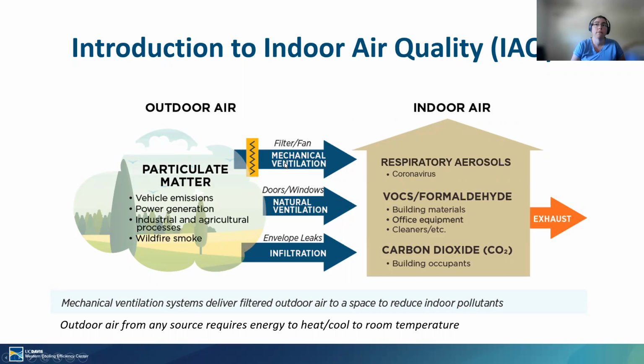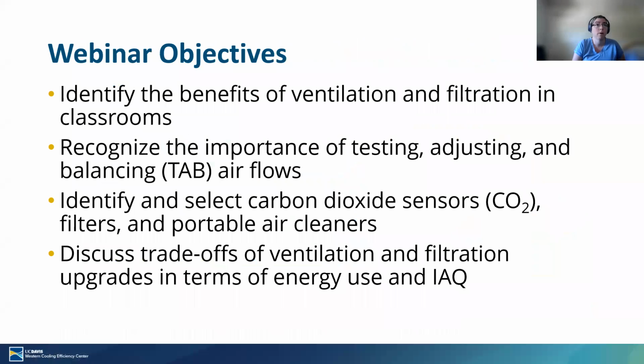The benefit of mechanical ventilation is that we can filter it, whereas that just doesn't happen with infiltration and with open doors and windows. Outside, we have to be concerned about particulate matter, which has important implications for human health, and that can be generated by more constant emissions from vehicles and power generation and ag processes. But then we also have now the issue in the West of intermittent wildfire smoke. And it should be pointed out that regardless of where this outside air comes from, if we're trying to maintain an indoor environment, we have to heat and cool that air somehow if we want to stay comfortable.